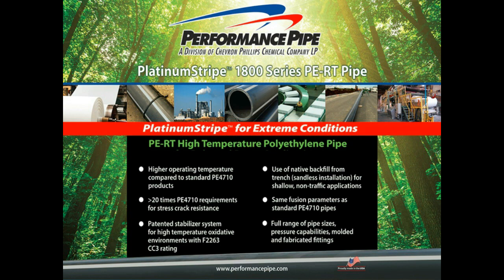It has a high coefficient of expansion, but due to the fact that the modulus is low and actually gets even lower as the temperature gets warmer, it's very easy just to restrain that movement. And commonly for buried applications, with a modest temperature change, the soil restraint between the pipe and the soil is enough to anchor the pipe in a buried application.